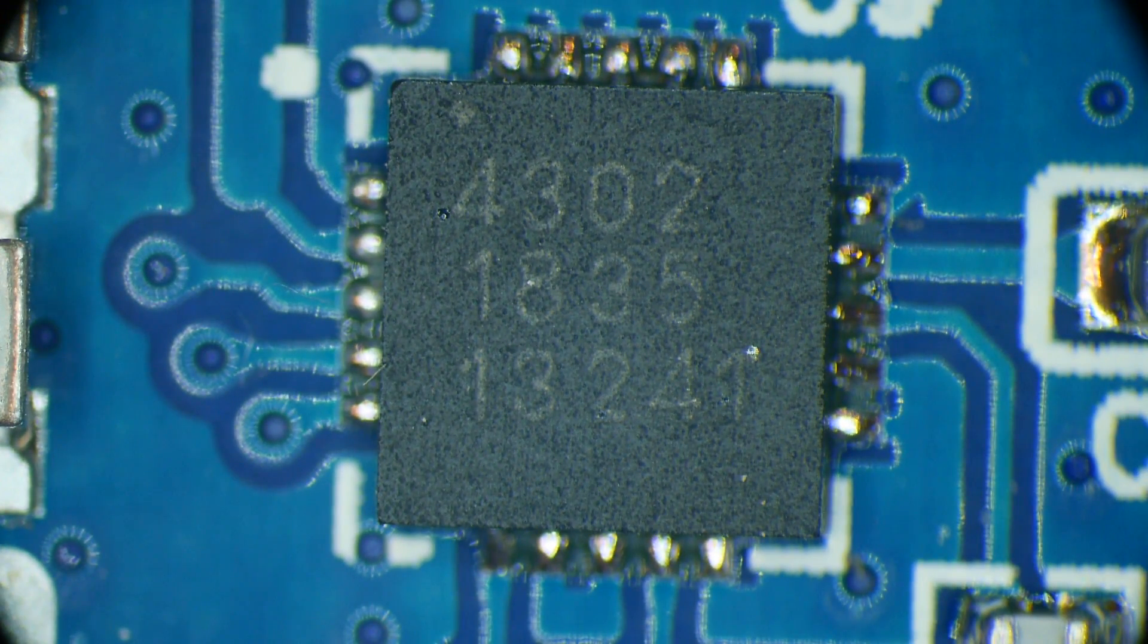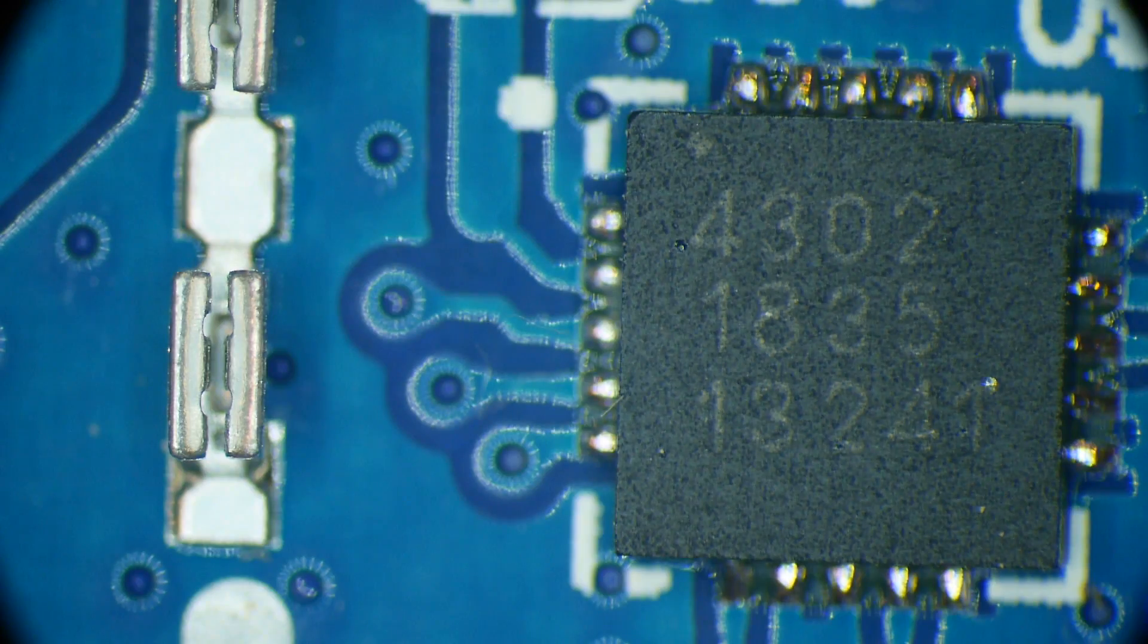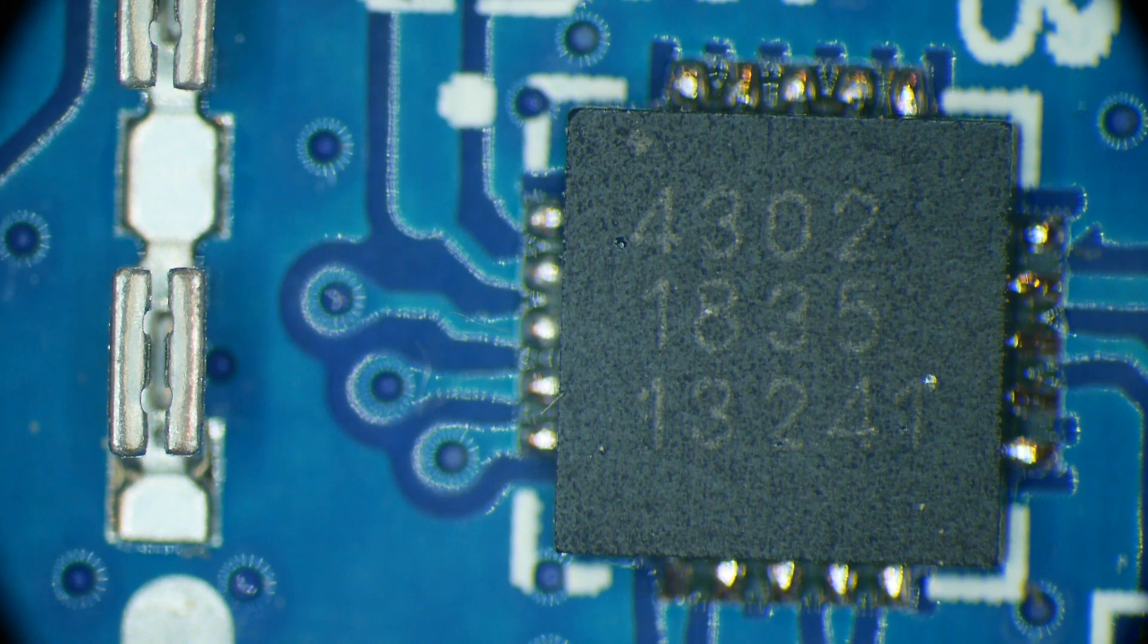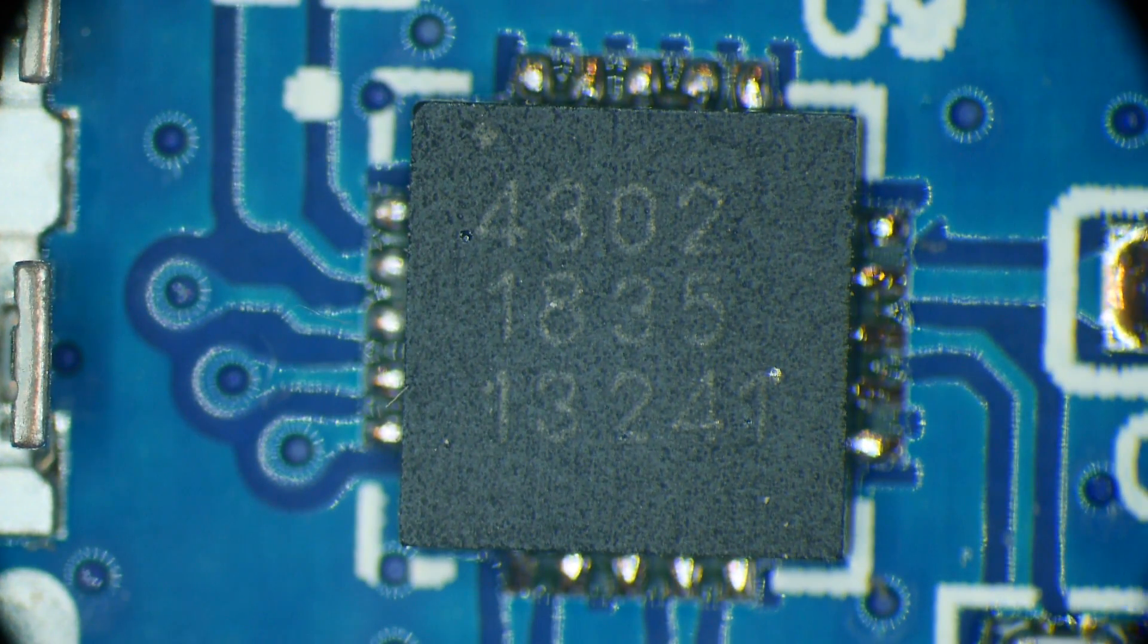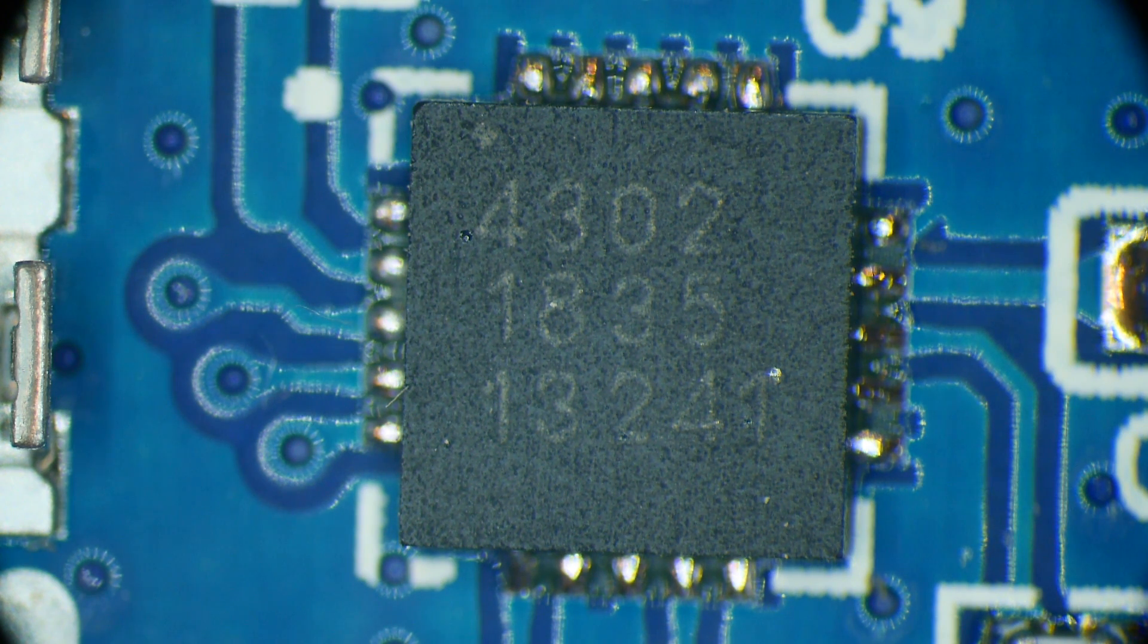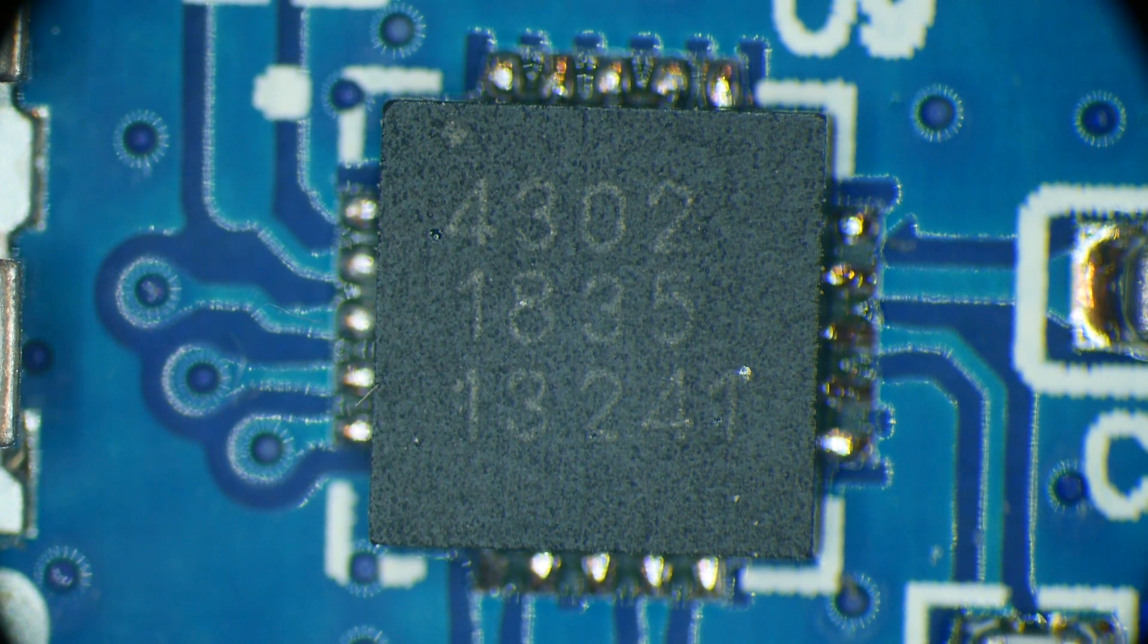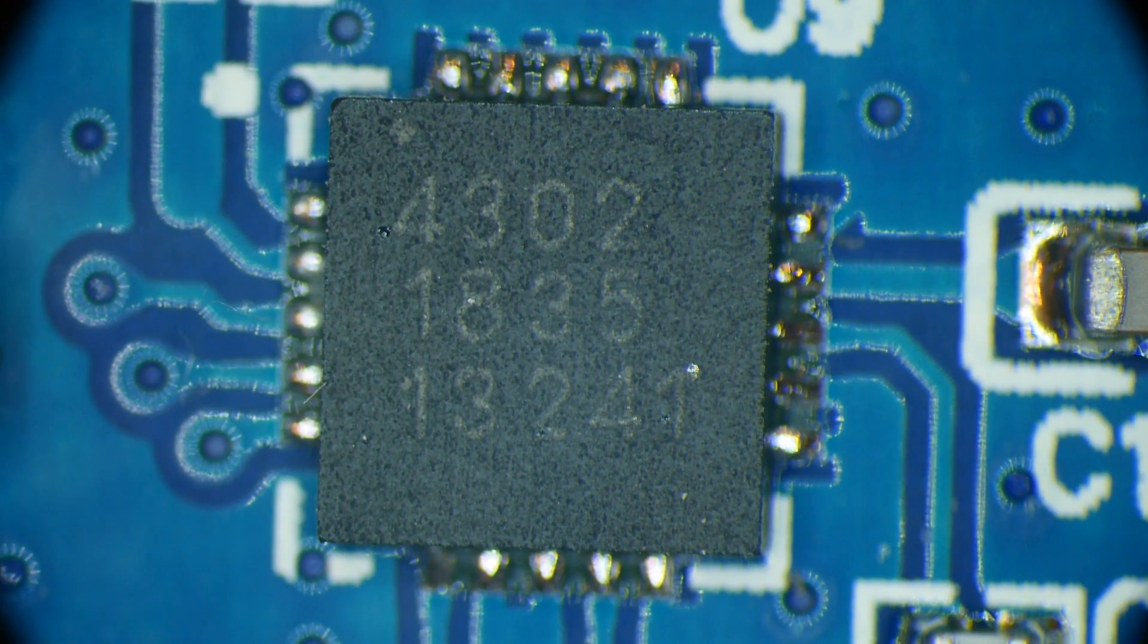But it also has the capability of clock and data for serial communication, and that's how this one's being used. All of the parallel pins are grounded and then the three little pads there off to the left, two of those are clock and data, so it has serial input. If serial input's working with all the other attenuator values and not 4 dB, then the chip is bad. There's no way that solder can cause this type of problem, so it is a bad chip.